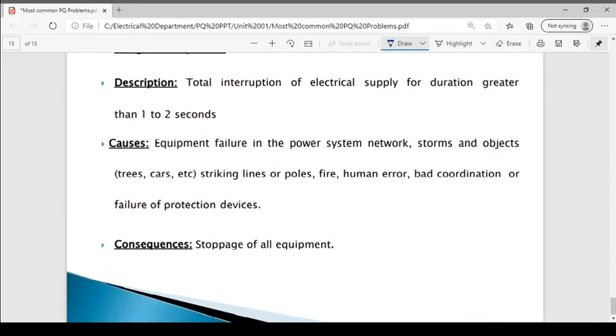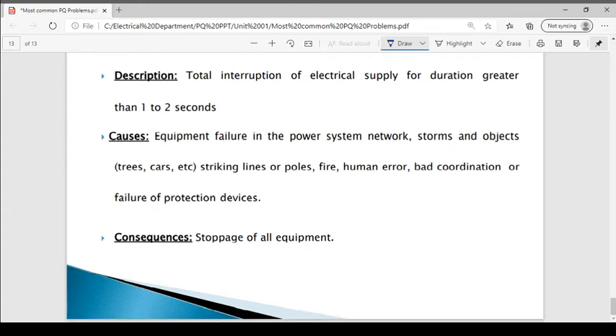A long interruption. A total interruption of the electrical supply for a duration greater than 1 to 2 seconds is a long interruption. The causes are equipment failure in the power system network, storms, objects like trees and cars striking the lines or the pole, fire, human error, and bad coordination or failure of the protection devices. And the consequence is very common: stoppage of all the equipment. So these are basically referred to as the simple power quality problems, as we discussed in detail over the last couple of video lectures.